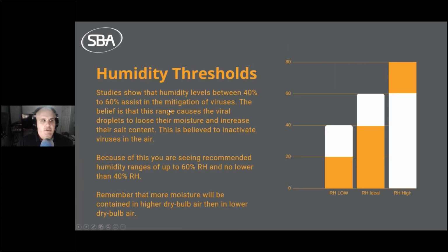Humidity thresholds. Studies show that humidity levels between 40 to 60% assist in the mitigation of viruses. Basically, how this works is that the viral droplets at 40 to 60% relative humidity lose their moisture and increase in their salt content. And then this inactivates viruses in the air, right? It causes the viruses to become inactive.